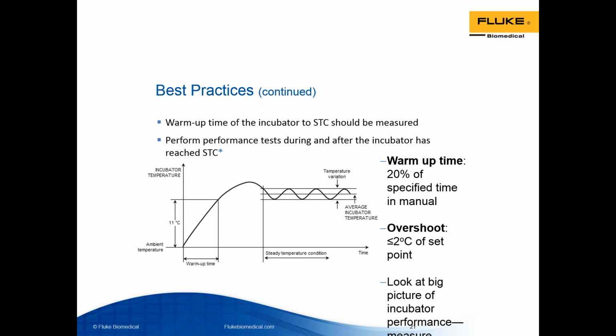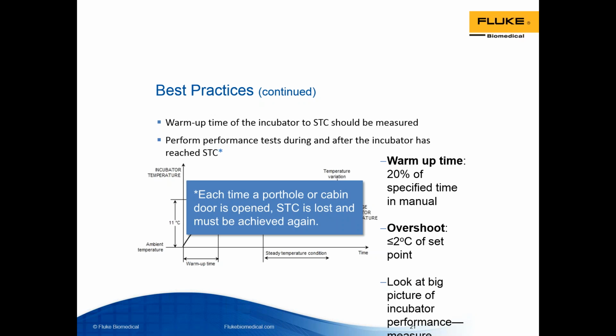So simultaneously measuring each parameter, I apologize, it looks like it went off the screen a little bit, but simultaneously measuring each parameter during the warm-up time and after STC helps give us an insight into how the device is running as a whole and where problems might be occurring if the incubator isn't functioning properly. So keep in mind, though, that each time a porthole or a cabin door is opened, the STC is technically lost and must be achieved again. So it's important to do your testing all at once, simultaneously if possible, and not interrupt the test environment.